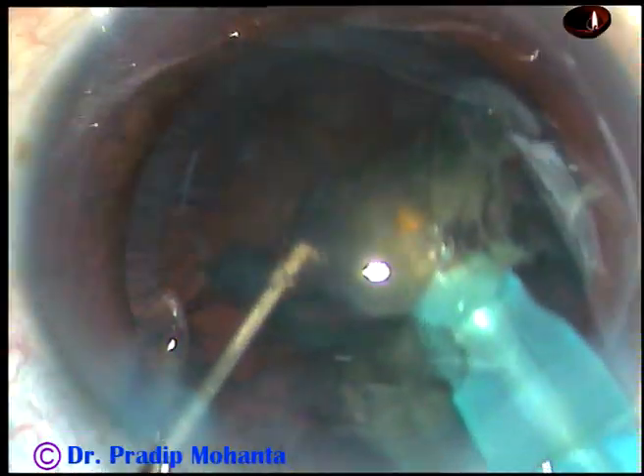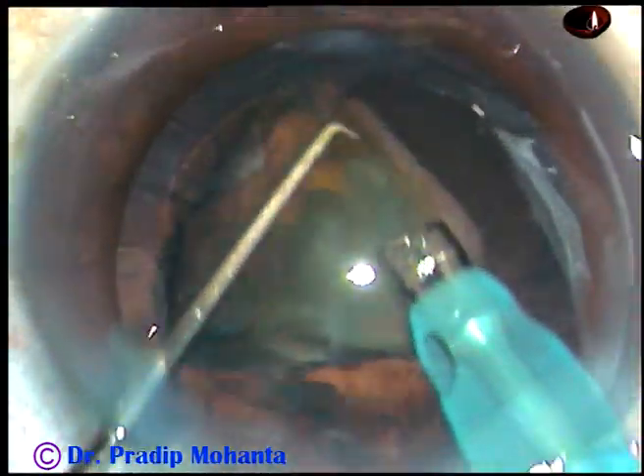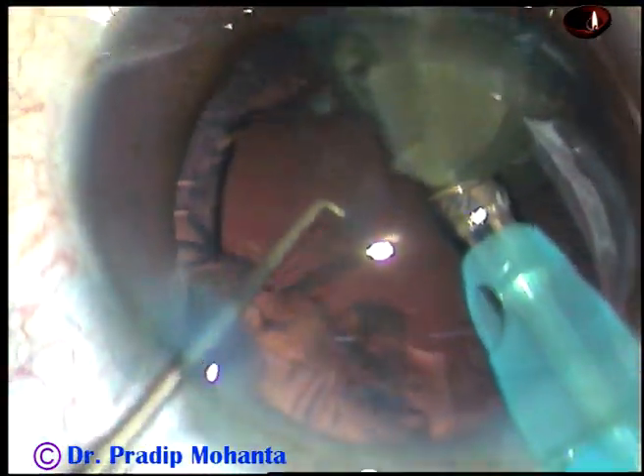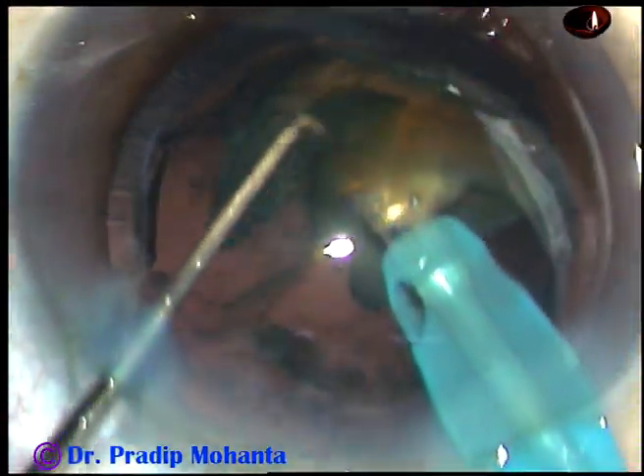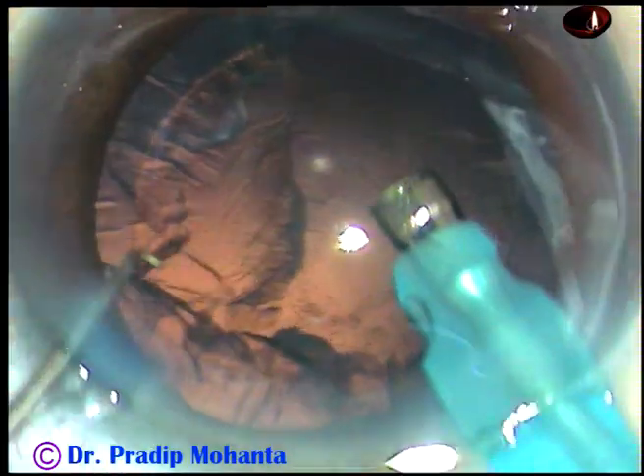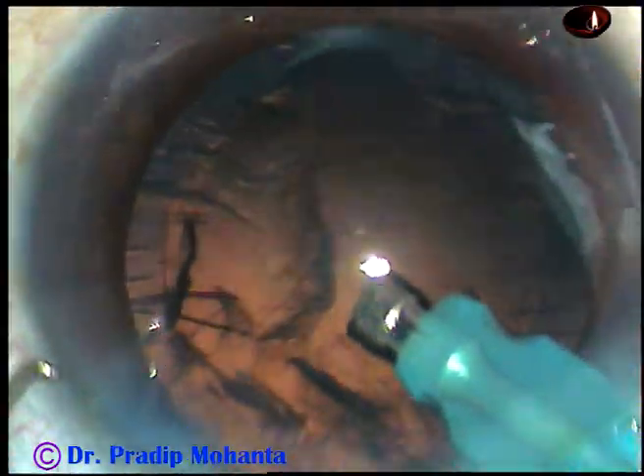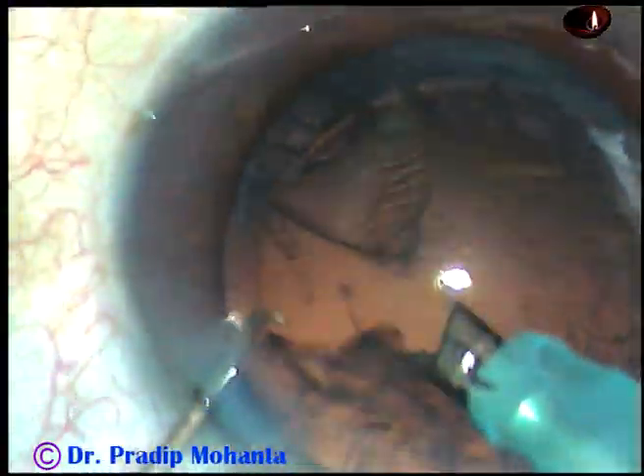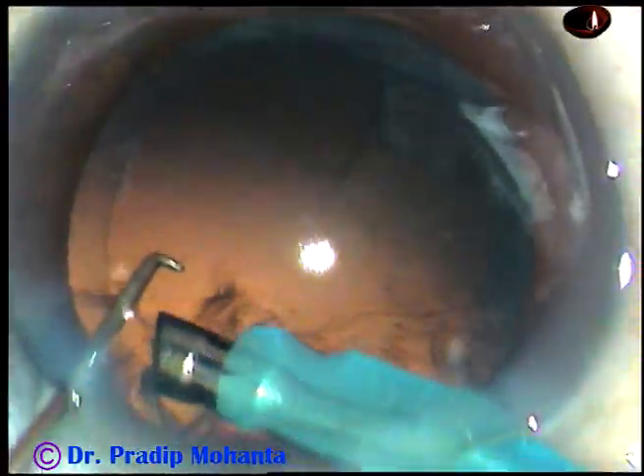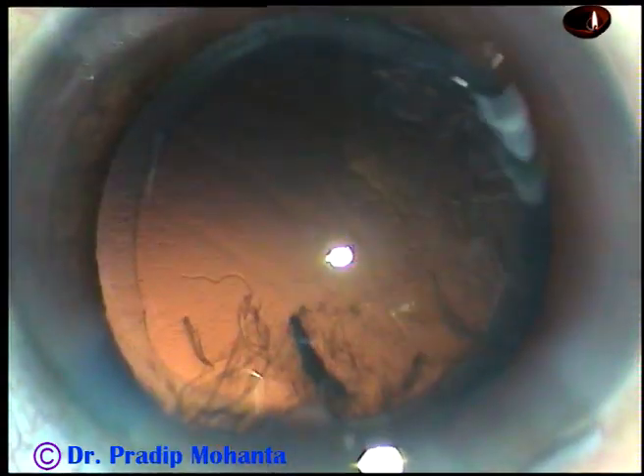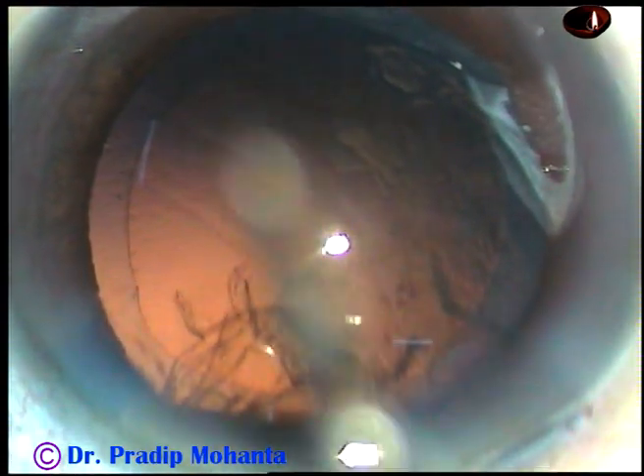And now after cracking, I am in Phaco 2 mode where the vacuum is 400, flow rate is 40 and ultrasonic energy is 70%. And this is the last piece. At this time we can reduce the parameters. We can go to Phaco 3 mode where the vacuum is 300, flow rate is 30 or 25 and ultrasonic energy is about 50%. And now the video is at 150% speed after management of the nucleus.